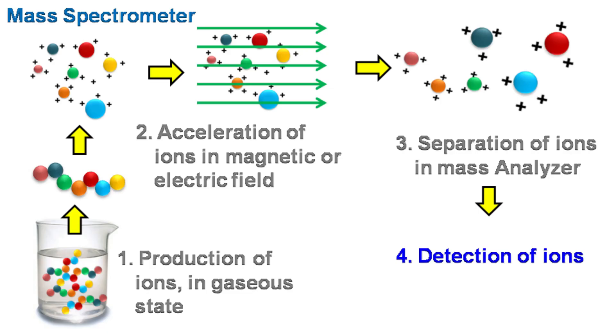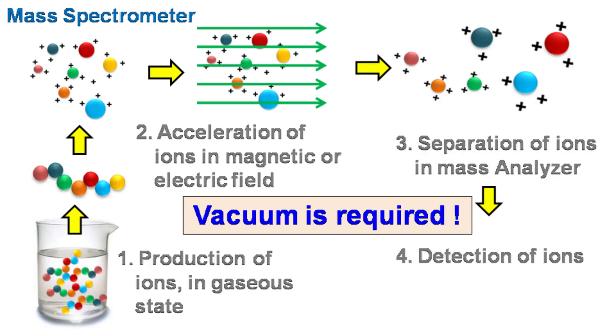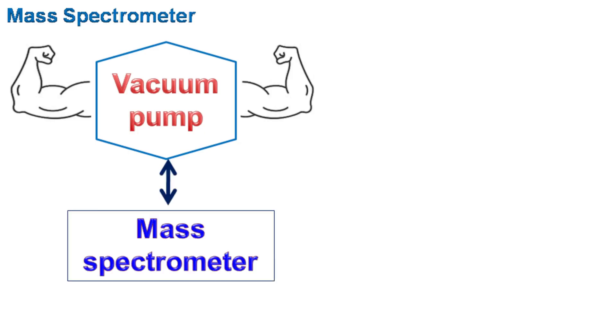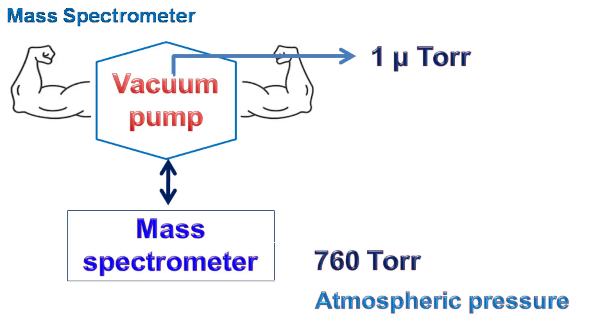In this technique, because we are dealing with production and detection of ions, we need to have very strong vacuum. Without vacuum, the ions produced will collide with air molecules and not reach the detector. The vacuum pump connected with the mass spectrometer generates a vacuum having air pressure of one micro torr.